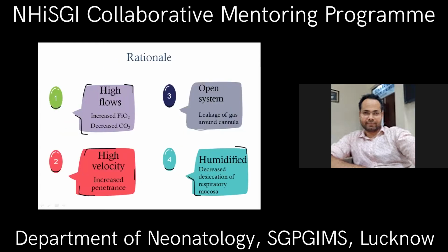So, what is the rationale? With high flow, there is increased FiO2 and decreased levels of carbon dioxide. And with the high velocity of the gases in high flow, there is increased penetrance of the oxygen. It is an open system and hence there is leakage of gas around the cannula, and no inadvertent extra pressure develops. And with humidification, there is decreased desiccation of the respiratory mucosa. I will talk about these concepts more in detail.